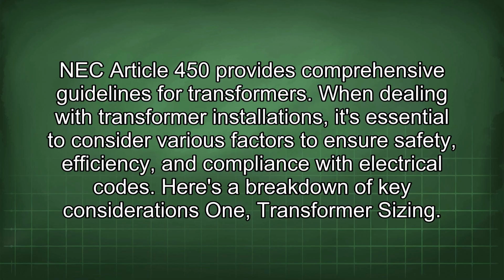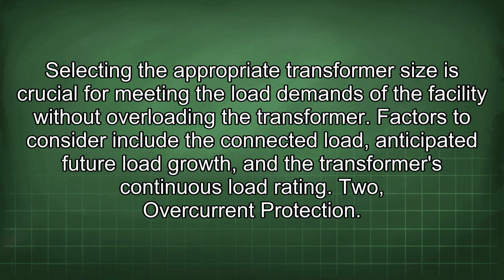When dealing with transformer installations, it's essential to consider various factors to ensure safety, efficiency, and compliance with electrical codes. Here is a breakdown of key considerations. 1. Transformer sizing. Selecting the appropriate transformer size is crucial for meeting the load demands of the facility without overloading the transformer. Factors to consider include the connected load, anticipated future load growth, and the transformer's continuous load rating.